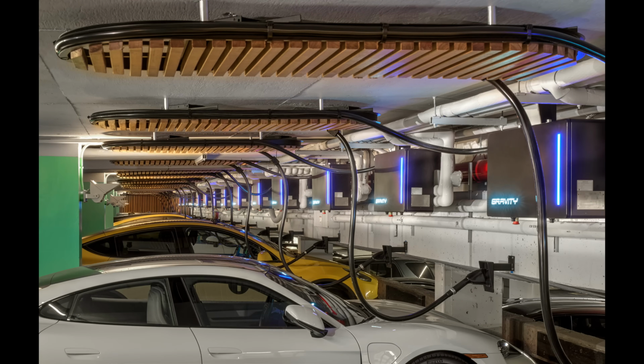Let's see what else. The cables apparently are able to support 500 amps continuous because they are both liquid and mineral oil cooled. So although they can do 500 continuous with that type of cable solution, they're able to burst up to 750 amps. So 1,000 volts, 750 amps gets you to 750 kilowatts.